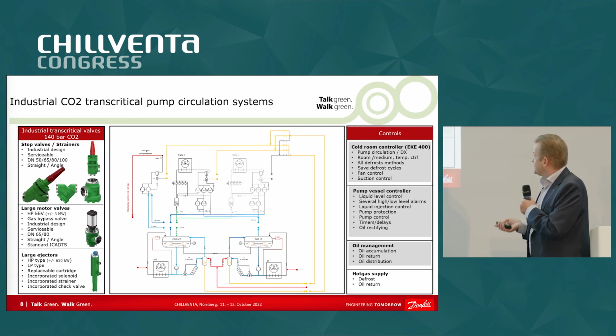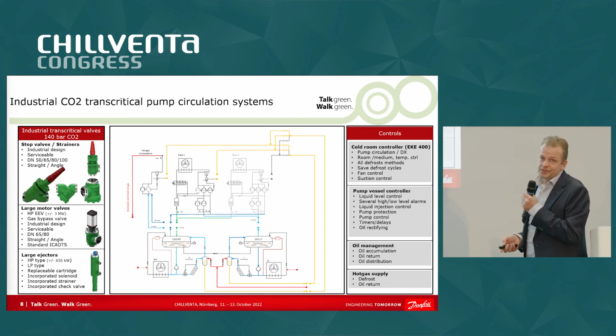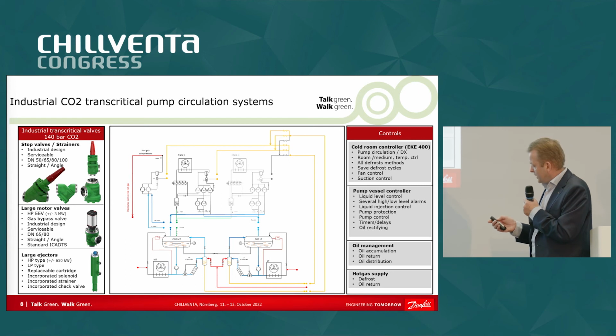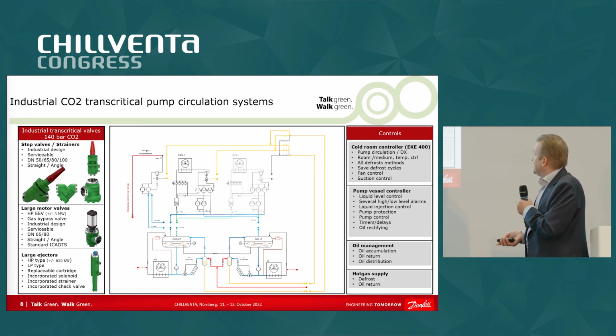And last but not least, hot gas defrost. Hot gas supply. If you want to do bigger systems, there's no way to not do hot gas defrost. That's the most efficient way of defrosting these systems. For that reason, we have in mind separate hot gas compressors to produce a controlled pressure and flow to defrost all these evaporators. But you need some controls for that. So that's all what we are working on to support these bigger transcritical industrial systems.